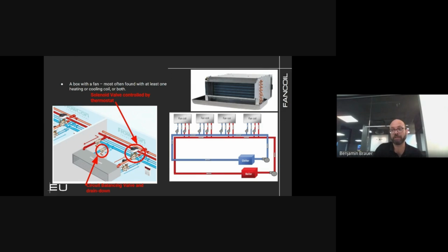Typically, we're talking like a 2-ton, 2.5-ton, maybe 3-ton for residence or typical commercial office space. The assembly, if you're looking at prefab assembly, it can be quite large. If the mechanical trade is to assemble that with threaded pipe, 6-way valve, the strainers, the pick V's and that sort of thing, they can get to the one I did for Amazon Post. They were probably 3 feet by 3 feet by a foot or so in depth.